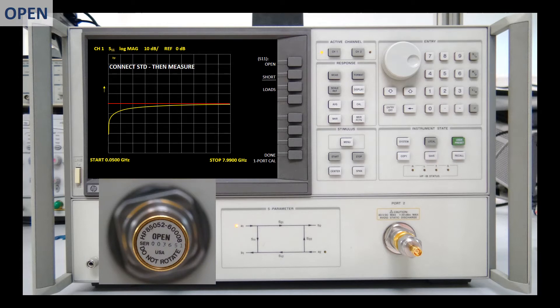I will connect now the open. We call it open, but it is not a true open. It is very difficult to build an open circuit at high frequencies due to radiation losses. This standard is just a short transmission line terminated with a capacitor. Now I press Open and the instrument starts the second measurement. And the label Open becomes underlined.